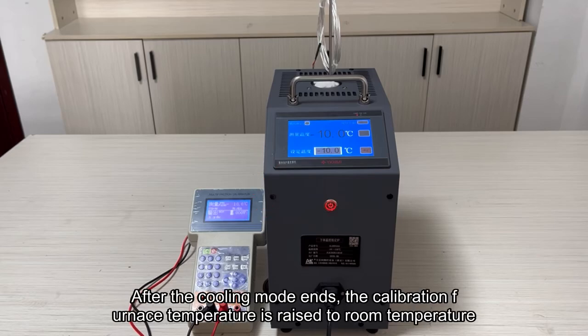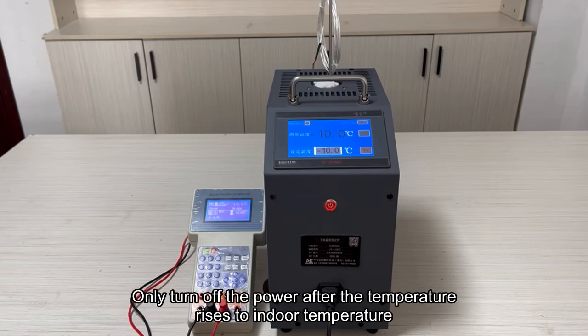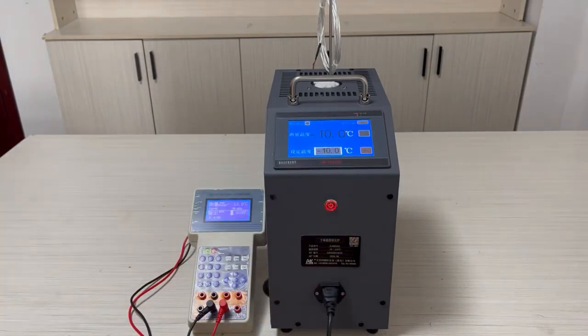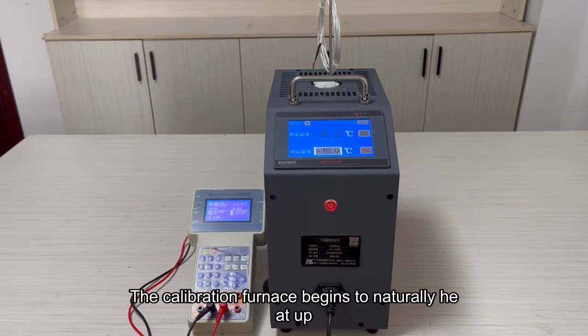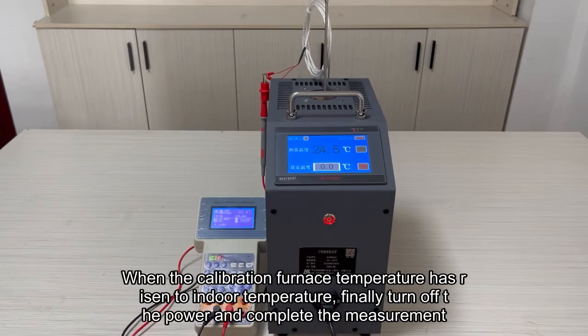After the cooling mode ends, the calibration furnace temperature is raised to room temperature. Only turn off the power after the temperature rises to indoor temperature. So click the Stop button first. The calibration furnace begins to naturally heat up. When the calibration furnace temperature has risen to indoor temperature, finally turn off the power and complete the measurement.